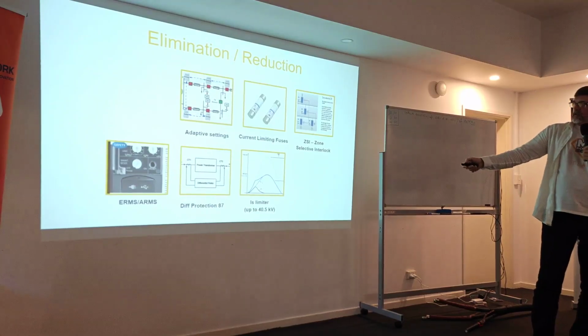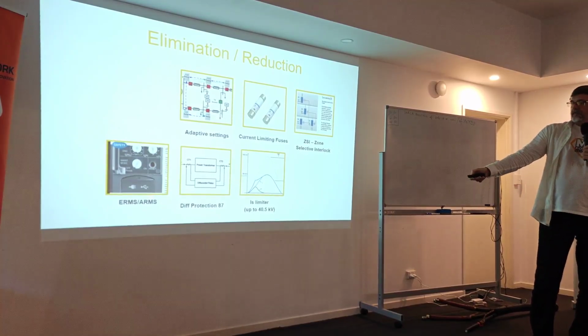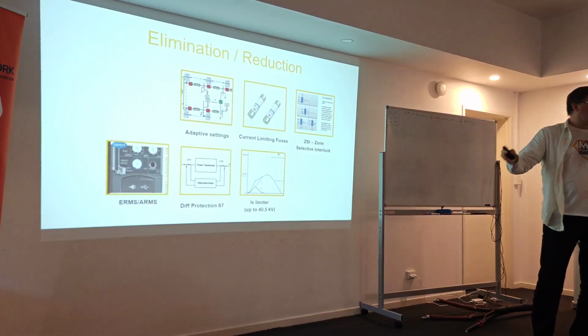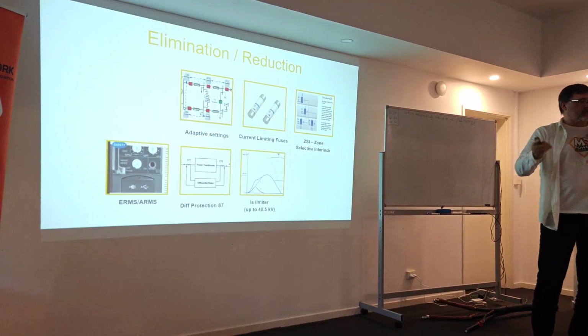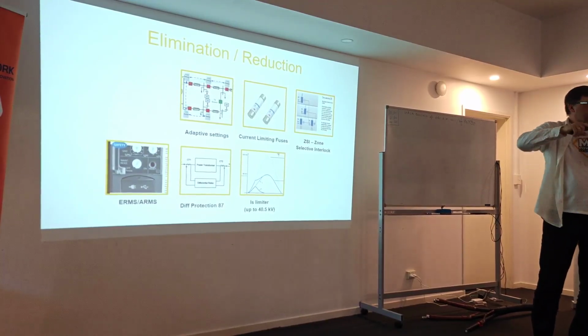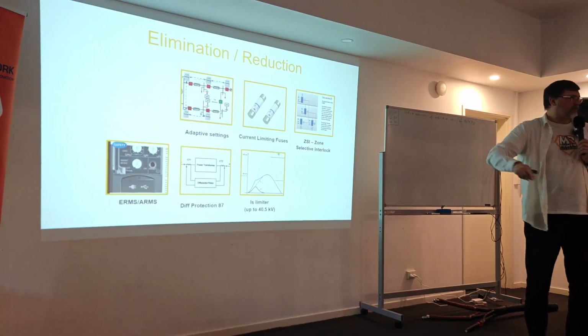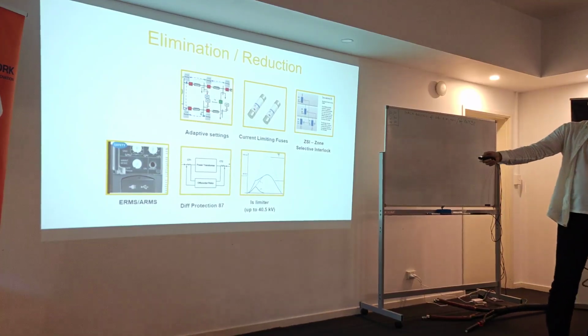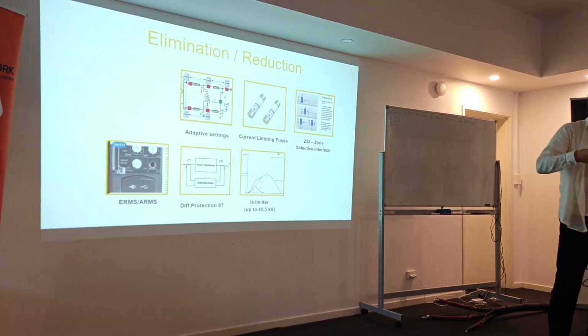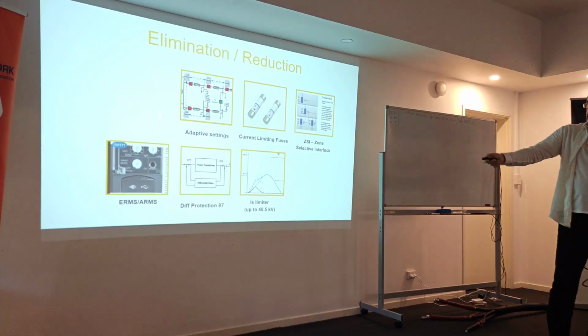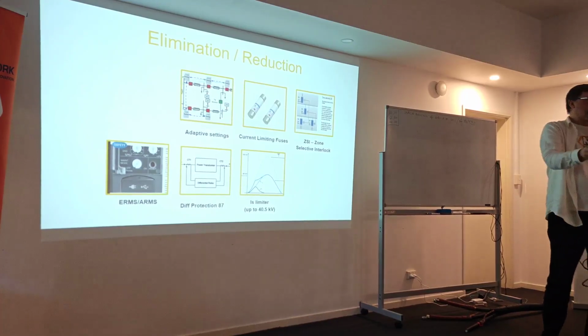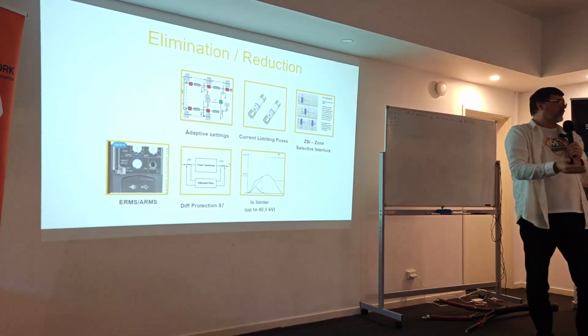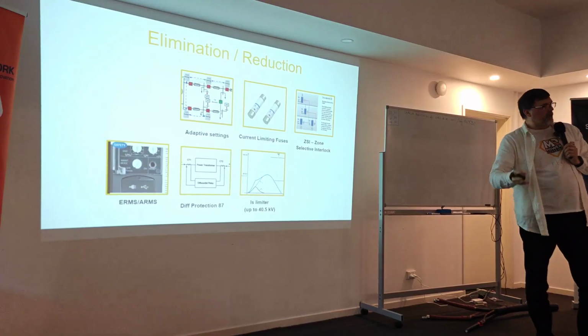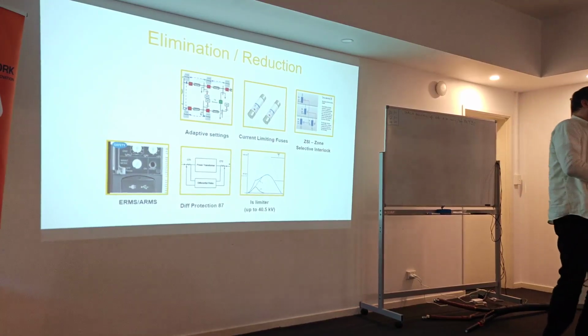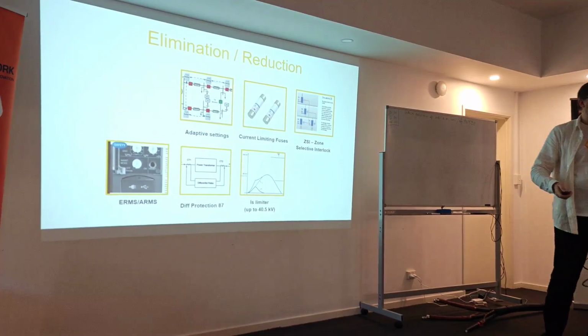Then there is a lot of other things. Adaptive settings is an interesting topic that I use, because ARMS, this is maintenance mode as a solution for the low voltage breakers. I will show you this as well. ARMS is because there's a trademark, energy reduction maintenance switch, arc flash reduction maintenance switch from I think Eaton and Schneider. But also we can do the same thing on the medium voltage, but on medium voltage you have to program it yourself in the relay. And I will show you how this can work. Adaptive settings is generally like reprogramming the relay because of the configuration of the network. And sometimes you have to do it, and the relay can do it automatically. When something changes, there's a signal, and like, okay, I'll reprogram for lower settings, higher settings, because you now run 2 lines instead of 1.